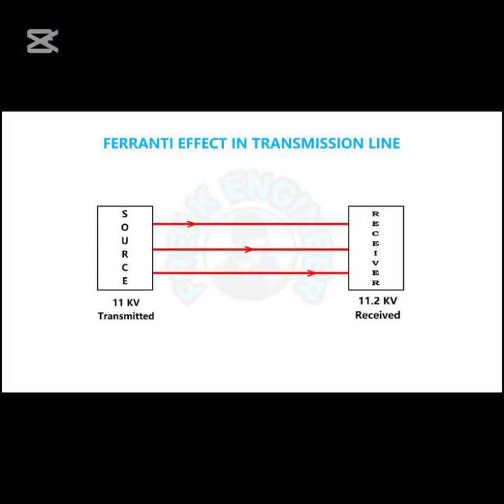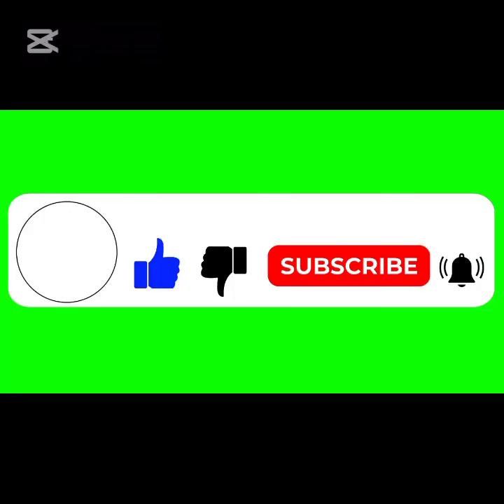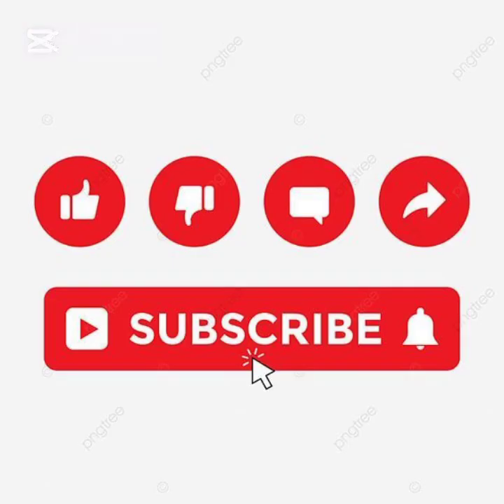Key points to note about the Ferranti effect: one, it causes a rise in voltage resulting in a negative voltage difference between the sending and receiving ends; two, the effect is directly proportional to the square of both frequency and line length; three, increasing transmission line length and supply frequency amplify the Ferranti effect; four, short transmission lines and high voltage DC transmission lines are not susceptible; five, the effect is most significant under no load or light load conditions; and lastly, the Ferranti effect occurs when the capacitor charging current exceeds the load current. Thanks for watching — please like, subscribe, and share your thoughts in the comments. Stay safe!